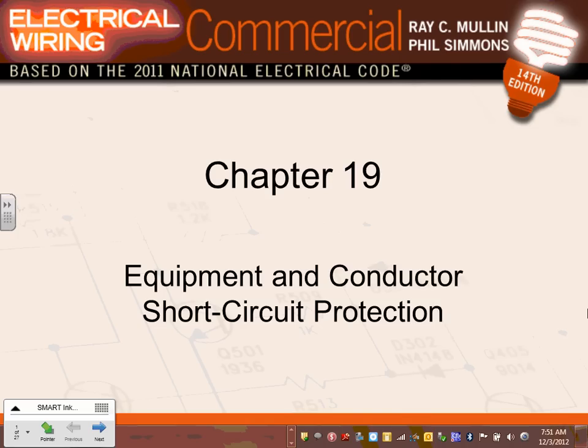Like we talked last time, guys, every piece of equipment in the electrical industry has a value called the withstand value. Very simple. If I am a switchgear, I will have an amp value that's called my withstand value. That's how much heat and magnetic force I can handle as a switchgear before I turn into a big ball of fire. It's as simple as that. We call it the withstand rating of equipment. How much short circuit current and ground fault current can I handle before I turn into a big ball of fire and start shaking?